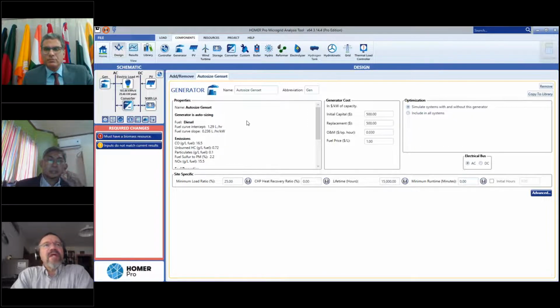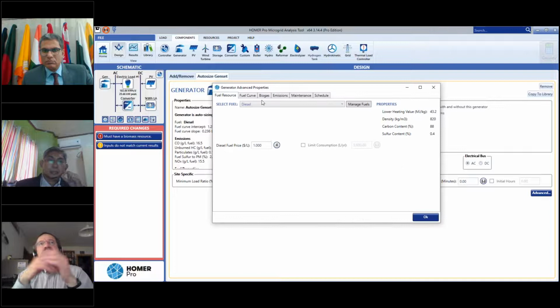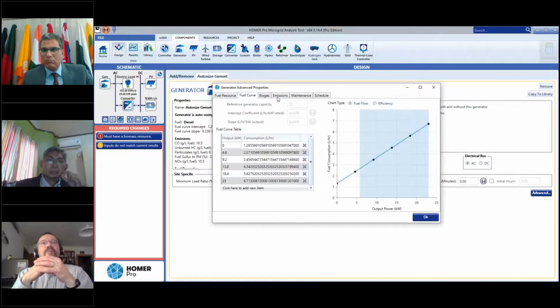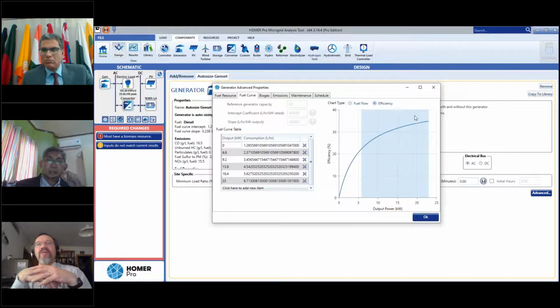Yeah, so that's the minimum load ratio, which you can see right there on the left. Every thermal generator has a minimum load, and it's not just for efficiency purposes - the efficiency drops off pretty dramatically, and in a minute Silver can show those efficiency curves. Show it now - click on efficiency, I think that's easier for people to think about.